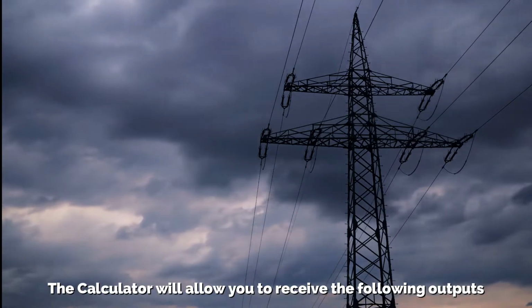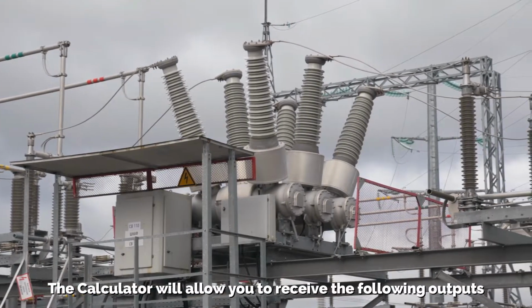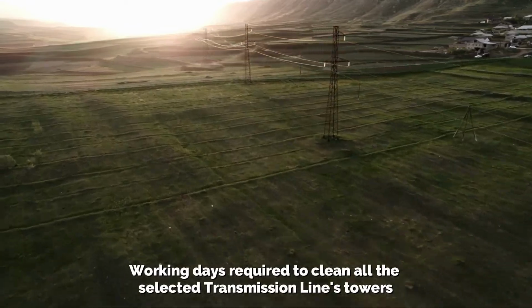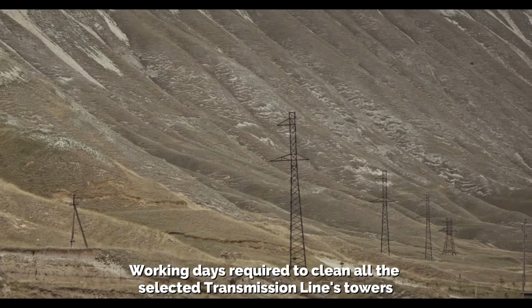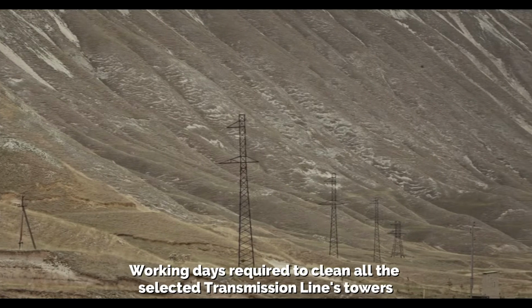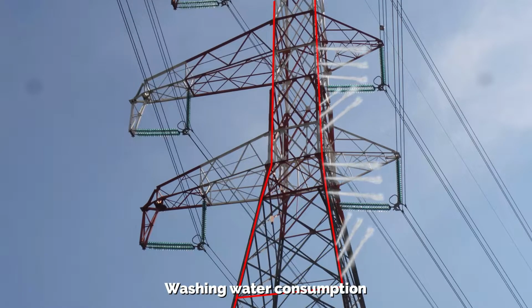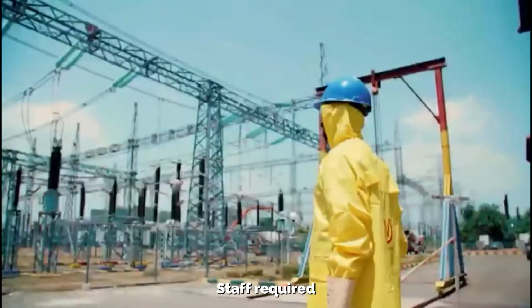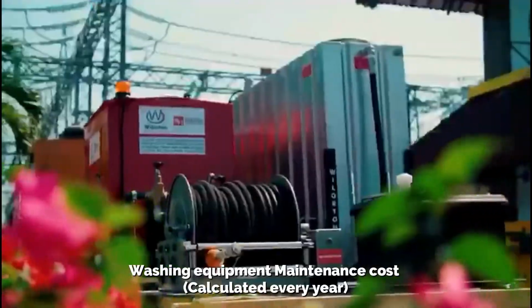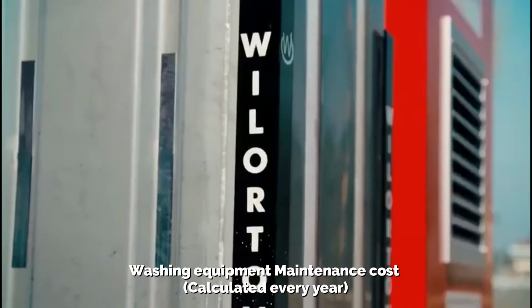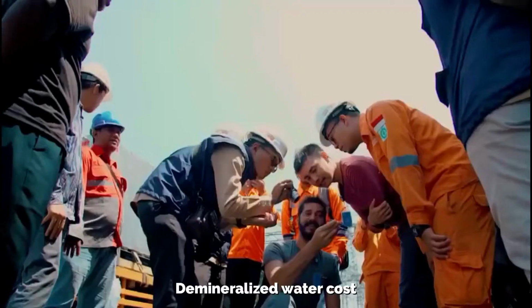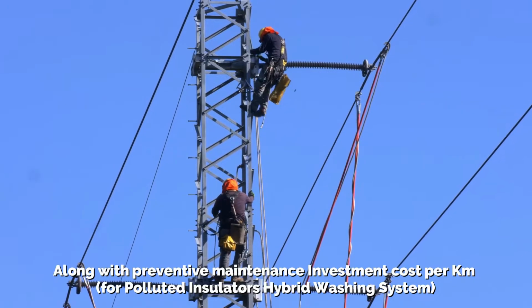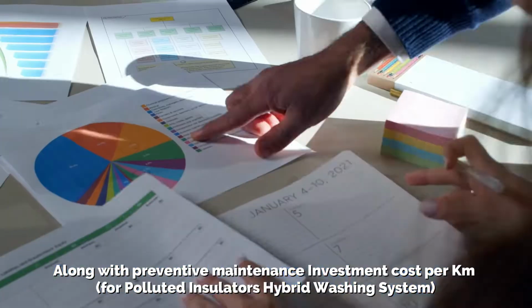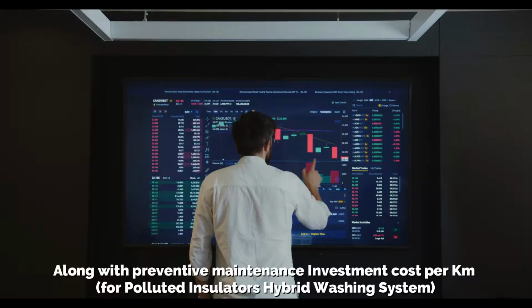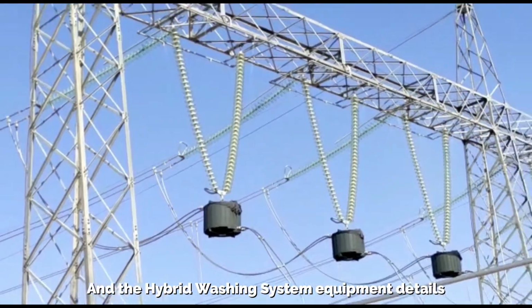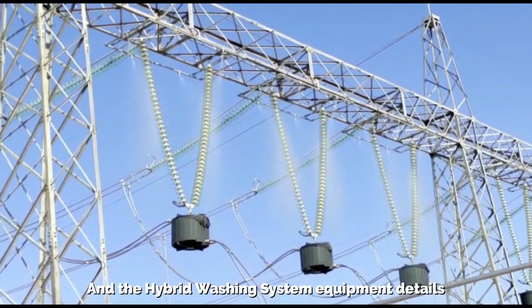The calculator will allow you to receive the following outputs: the daily number of towers cleaned, working days required to clean all the selected transmission line towers, washing water consumption, staff required, washing equipment maintenance cost calculated every year, and the demineralized water cost, along with preventive maintenance investment cost per kilometer for the polluted insulators hybrid washing system, and the hybrid washing system equipment details.